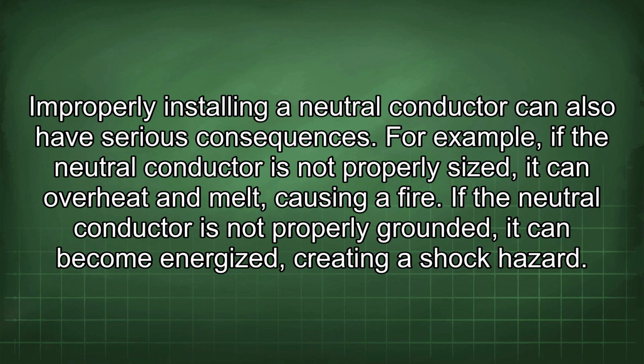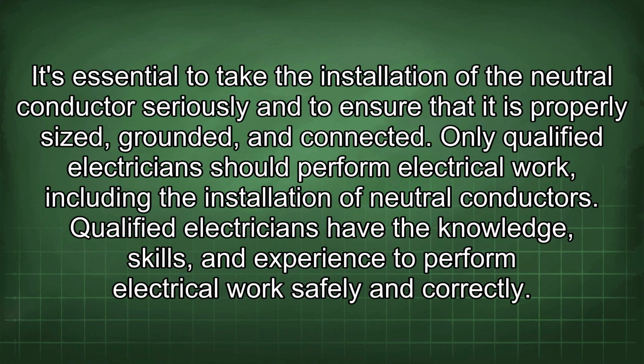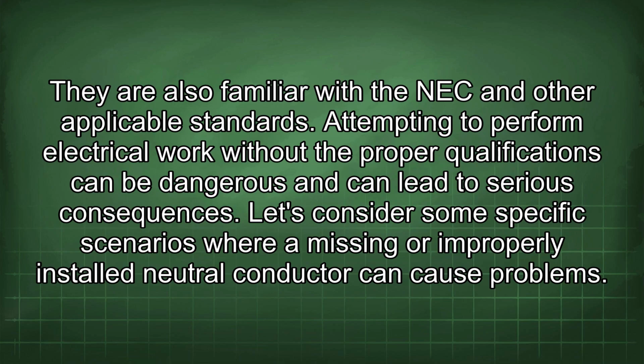If the neutral conductor is not properly grounded, it can become energized, creating a shock hazard. It's essential to take the installation of the neutral conductor seriously and to ensure that it is properly sized, grounded, and connected. Only qualified electricians should perform electrical work, including the installation of neutral conductors. Qualified electricians have the knowledge, skills, and experience to perform electrical work safely and correctly. They are also familiar with the NEC and other applicable standards. Attempting to perform electrical work without the proper qualifications can be dangerous and can lead to serious consequences.